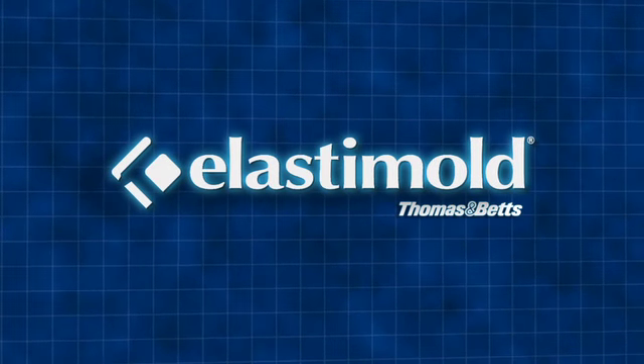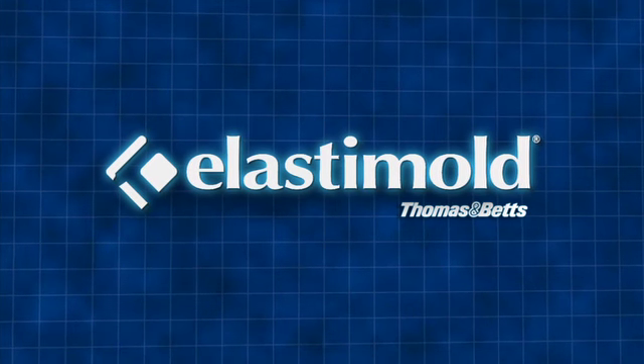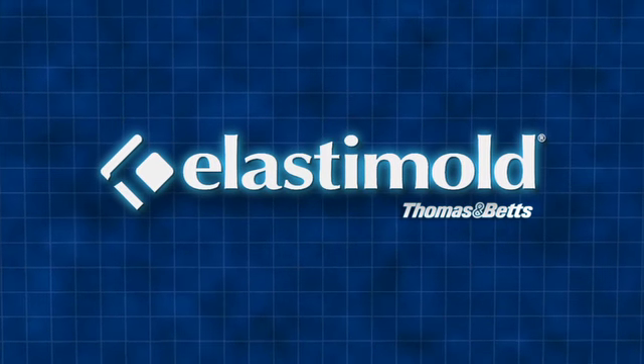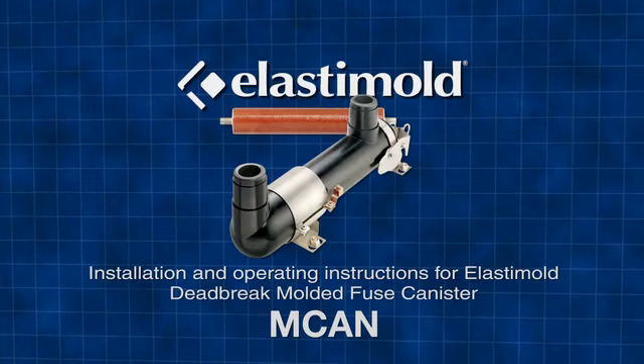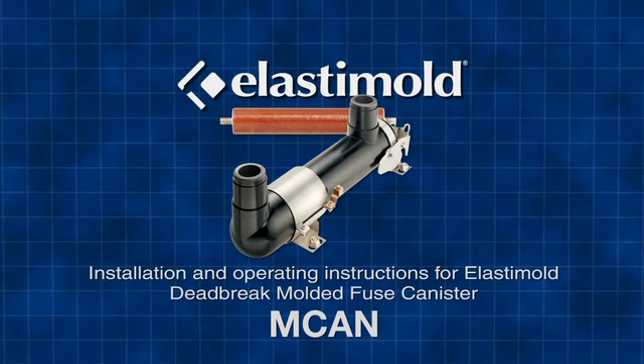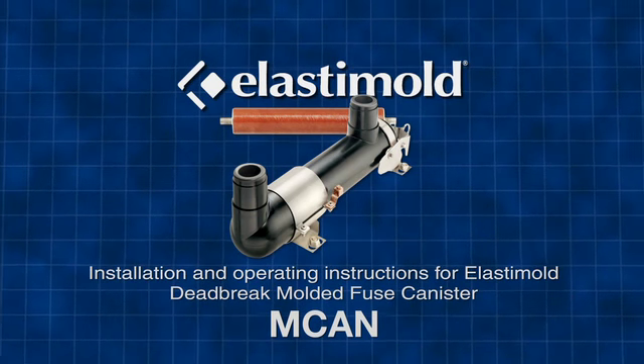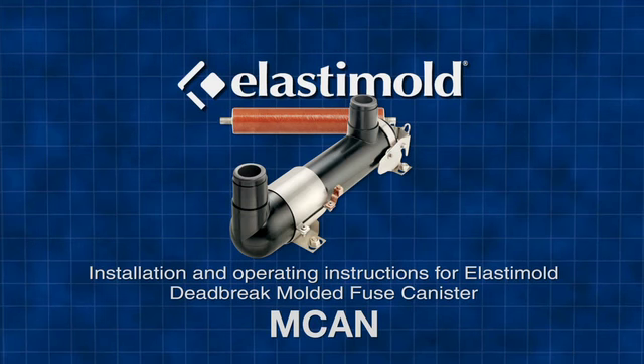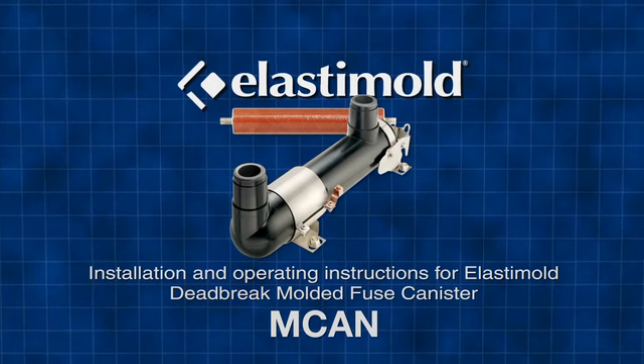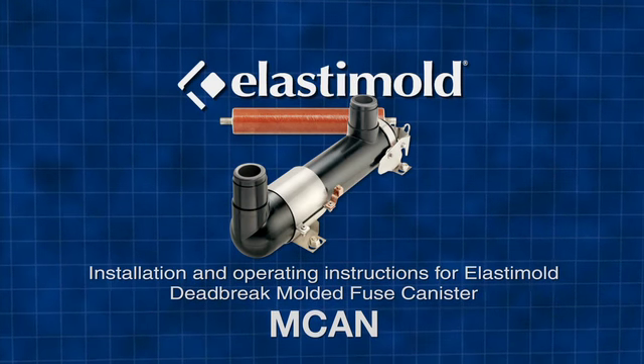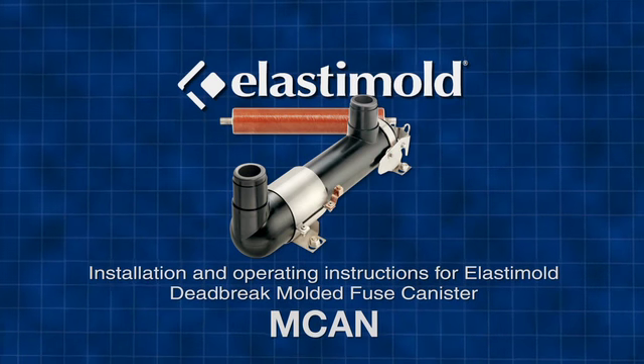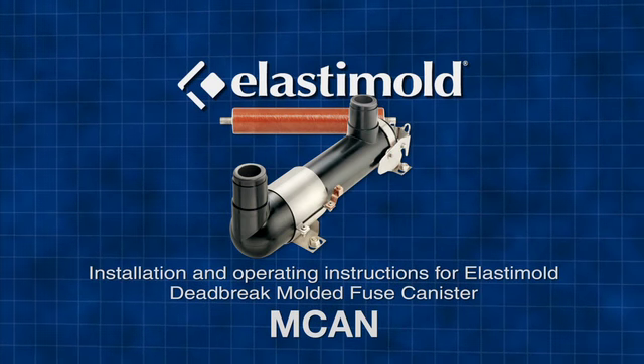The Thomas & Betts Elastimold brand, a recognized leader in pre-molded cable accessory components, presents installation and operating instructions for the Elastimold Dead Break Molded Fuse Canister, or MCAN.